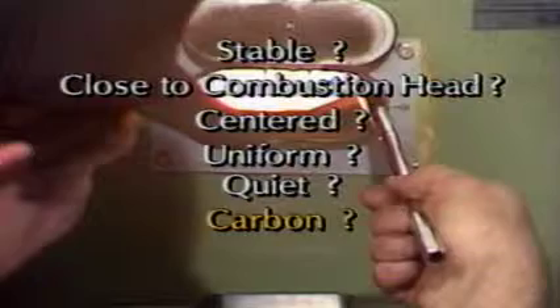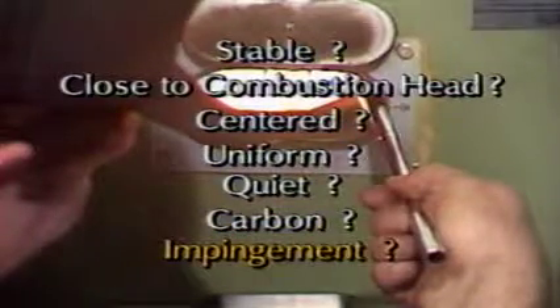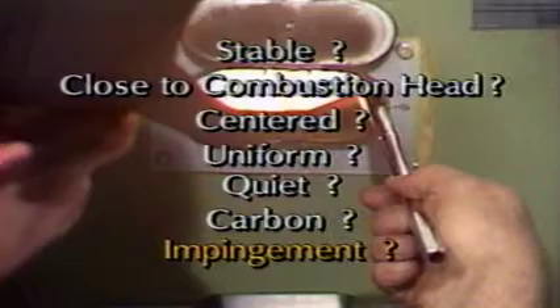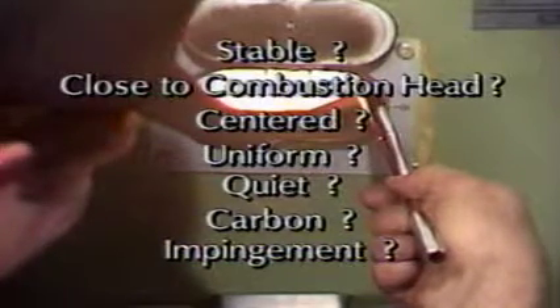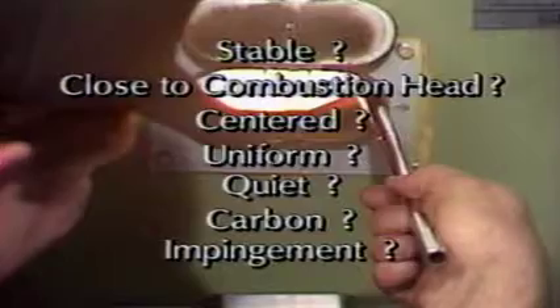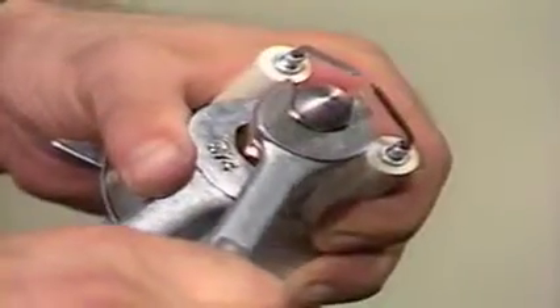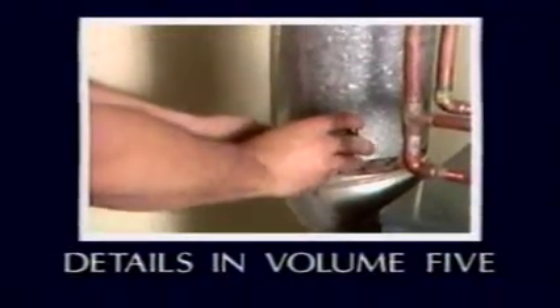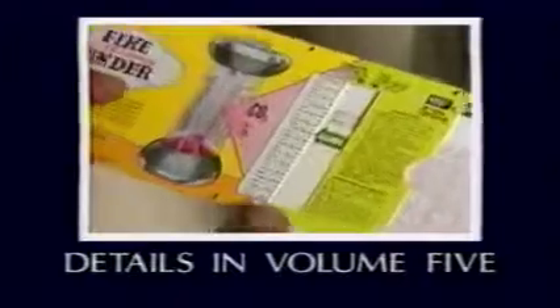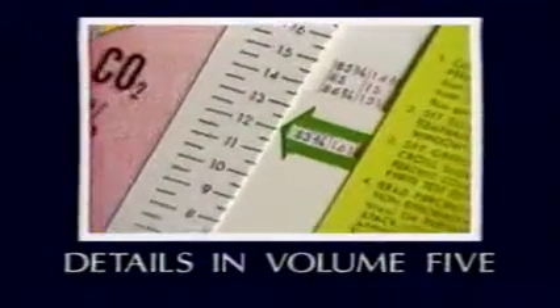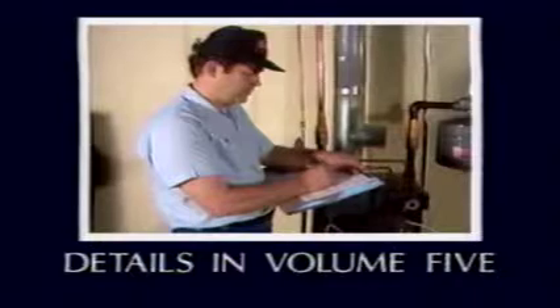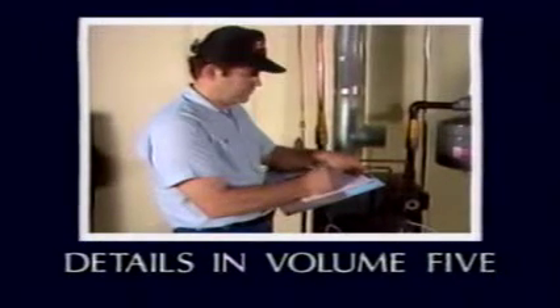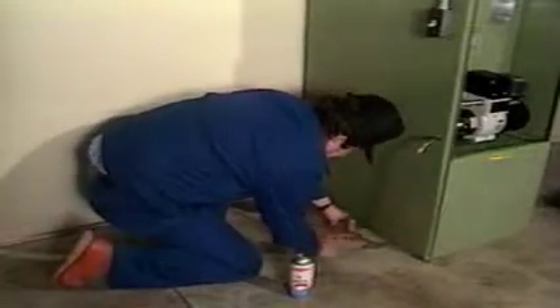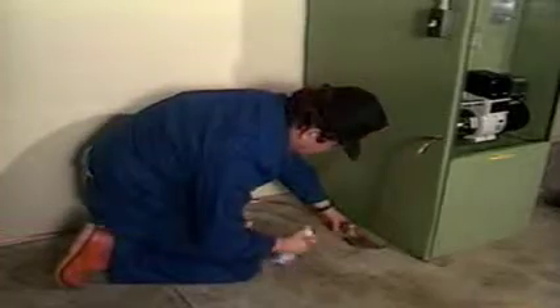Are there carbon formations on either the head or the chamber? Is there any impingement inside the chamber? These conditions can be caused by a defective or partially plugged nozzle. If this is the case, replace the nozzle with a new one of the same specifications. After you've found the source of the problem and you've corrected it, run the proper combustion efficiency tests as described in Volume 5, making note of any problems or operating conditions that call for routine or unusual servicing. Then, after cleaning up the area to better-than-found condition, move on to your next call.